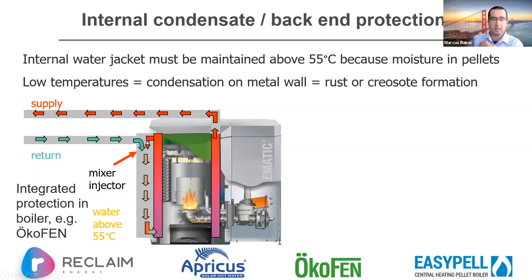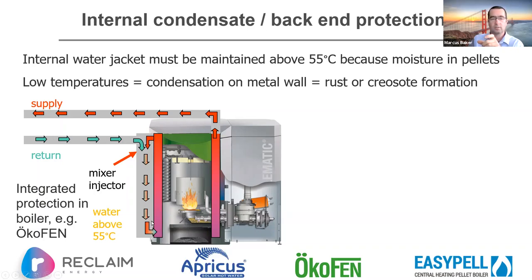The Ökofen boiler has an injector mixer — returning water is injected back in via an automatic varying mixer. When first starting with much more cold than hot water, a small amount is injected in; as the returning water increases in temperature, more is released until it's complete flow above 55 degrees returning water.